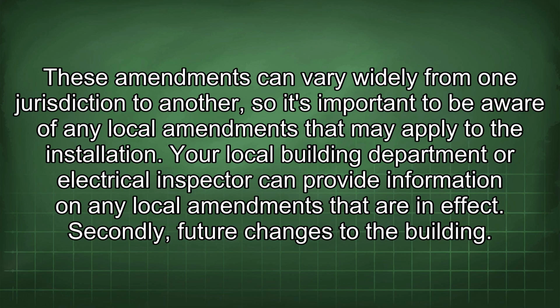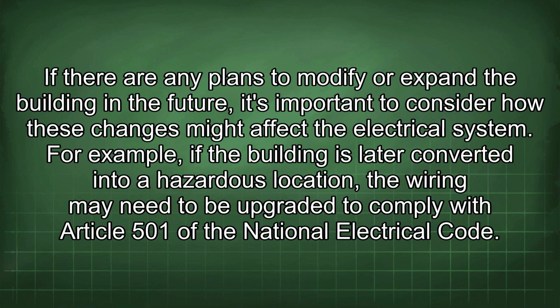Your local building department or electrical inspector can provide information on any local amendments that are in effect. Secondly, future changes to the building. If there are any plans to modify or expand the building in the future, it's important to consider how these changes might affect the electrical system. For example, if the building is later converted into a hazardous location, the wiring may need to be upgraded to comply with Article 501 of the National Electrical Code.